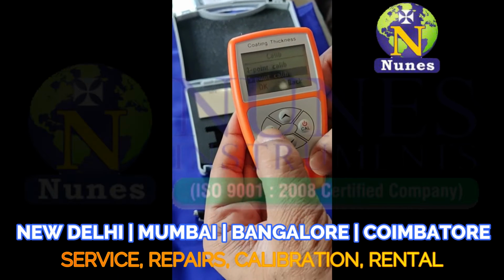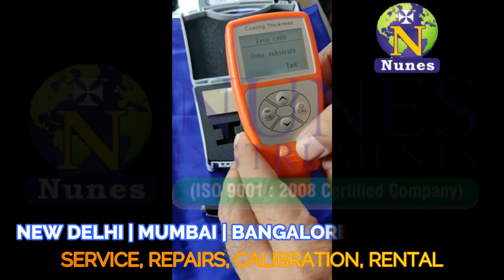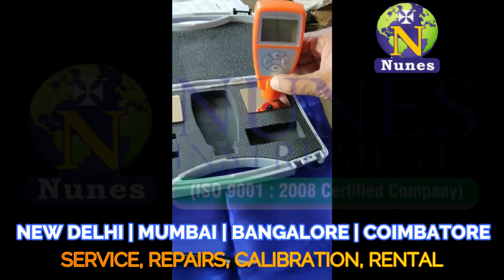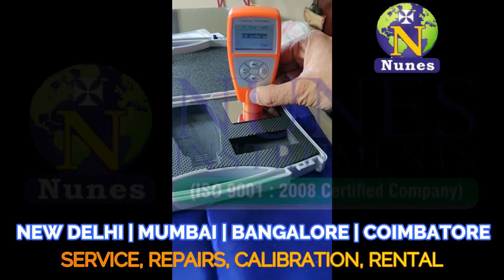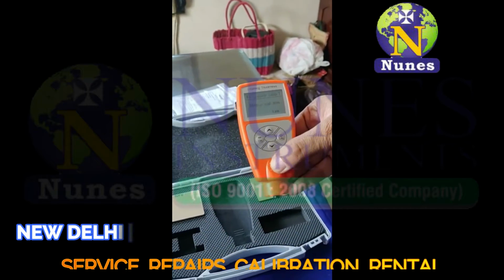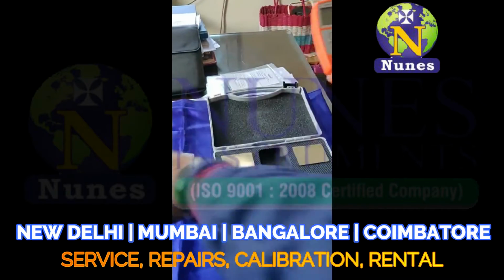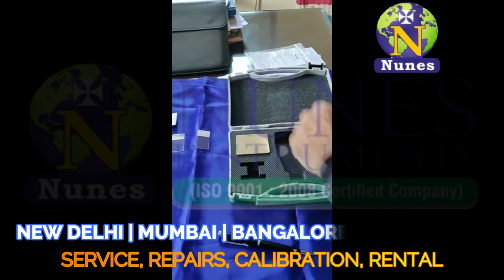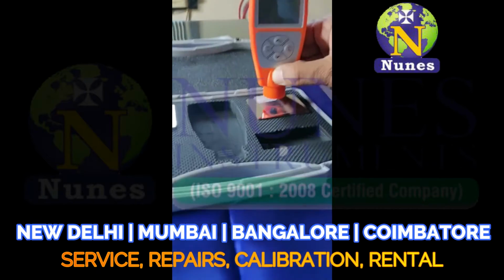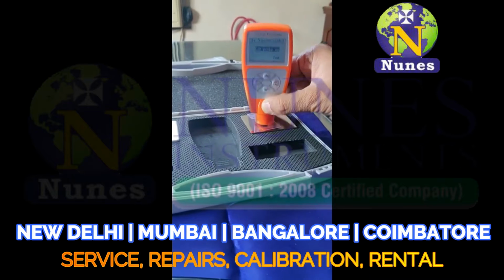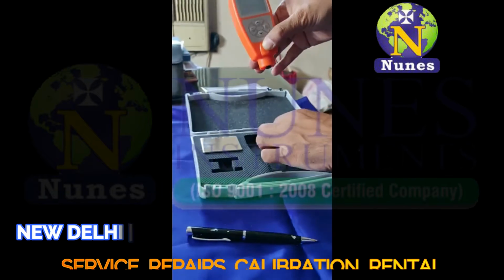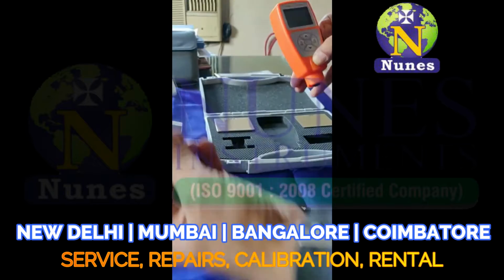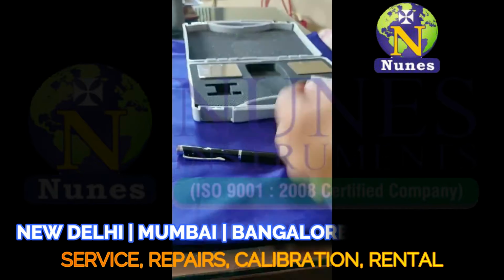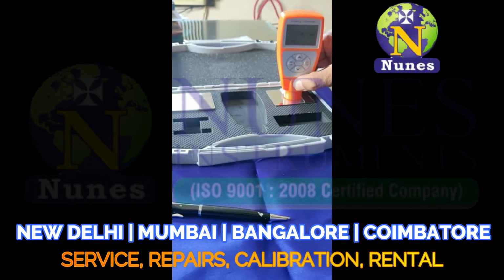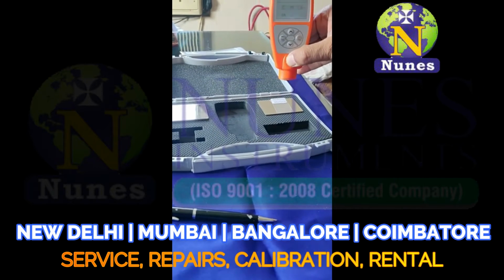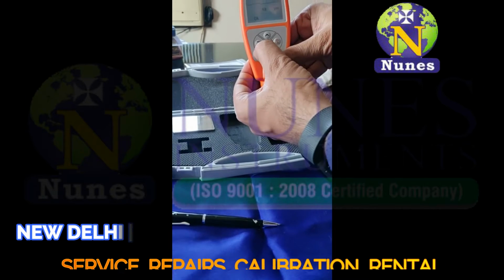So for a 5 point calibration we press OK. Now it says onto substrate. Lift probe, onto the standard film. It says number 1. Our standard film is 50 microns plus minus 1. Lift probe, it says 50. So calibrated. Next one is 98 microns. Lift probe. It shows 99, so we reduce by 1 and OK.